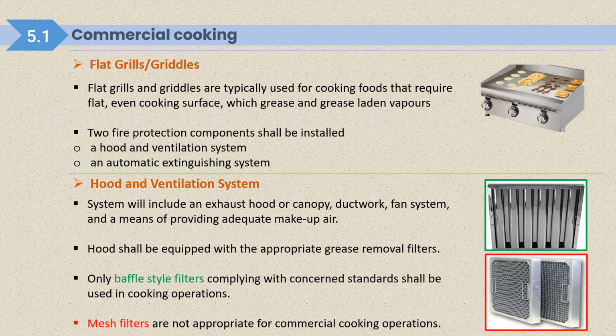Only Baffle style filters complying with the concerned standards shall be used in cooking operation. Above, you can see I have given a border of green color, so that is the only one allowed. Mesh filters are not appropriate for commercial cooking operation because mesh gets easily blocked. So this type of filter is not advisable to install.